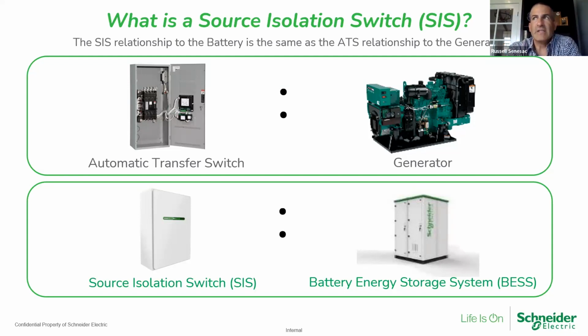So the way we should be thinking about this as an industry is: when I need a generator, I need an ATS. When I decide to implement a battery energy storage system, it's not an ATS anymore, it's an SIS that's required. The idea is that SIS will go through the same level of rigor, robustness, testing and certification that we've spent decades perfecting for an ATS. Because if I'm using that battery either in place of or before a generator, it's just as critical to provide power, and just as critical that that isolation switch has the same level of endurance and testing that the ATS has historically had.